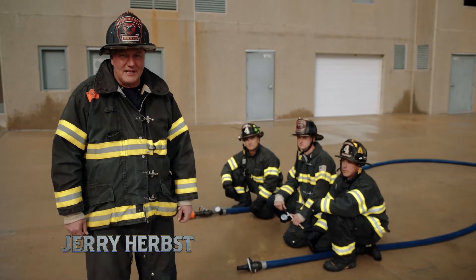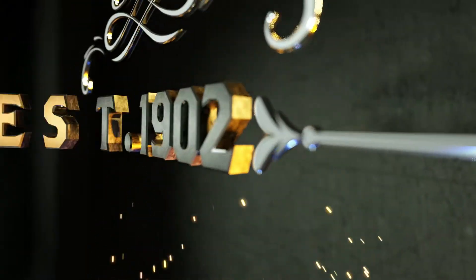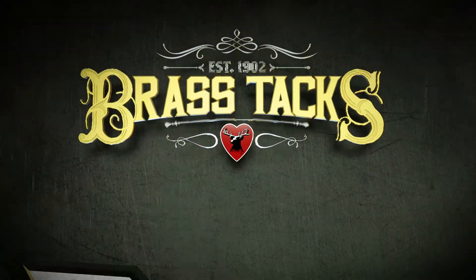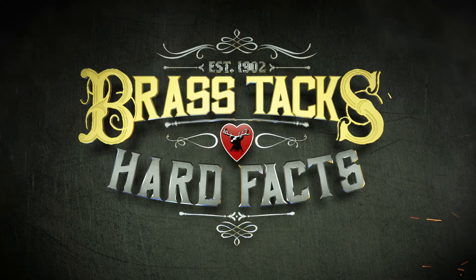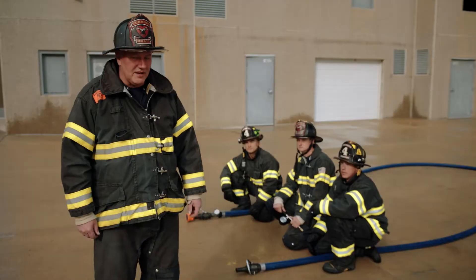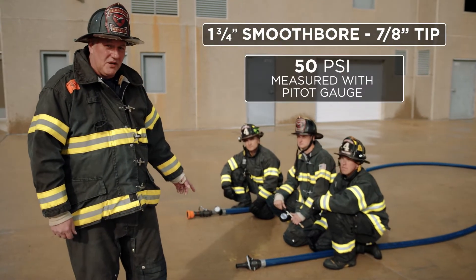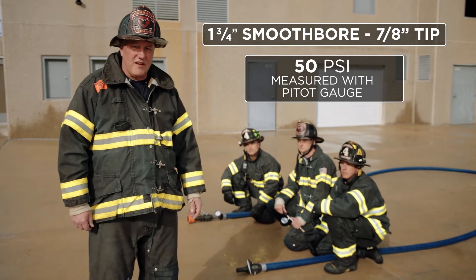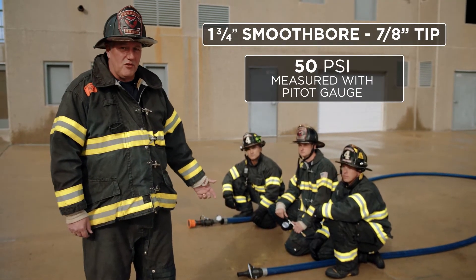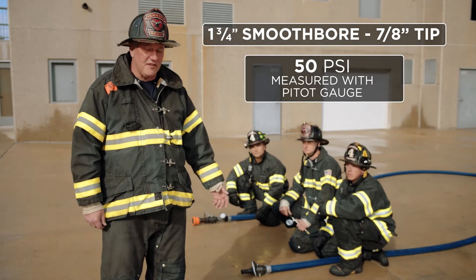I'm Jerry Herbst and we're drilling down to the brass tacks and hard facts on how to measure nozzle pressure. We've got this in a 1 3/4 inch line with shutoff and a smoothbore 7/8 tip on it. We're going to use a pitot gauge to confirm we have 50 psi in the exit portion of the nozzle. That'll correspond to our flow meter reading at 160 GPM and we'll know our system is operating at efficiency.